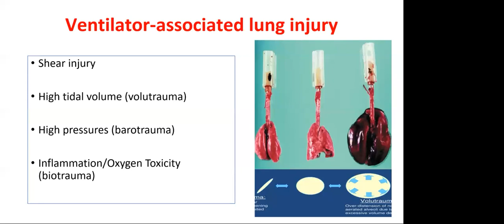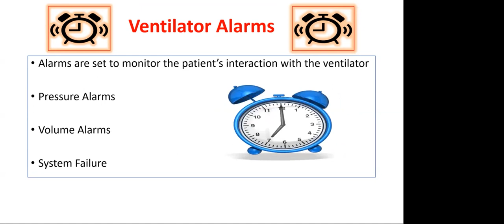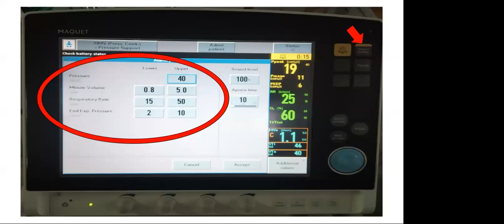So coming to the alarms. Alarms are mainly set to monitor the patient's interaction with the ventilator. There are alarms like pressure alarms and volume alarms. I already showed you the alarm profile, and I'm showing it again. Once you press here, alarm profile, you will come to pressure, minute ventilation, respiratory rate, and expiratory pressure. When do you want to get alerted? Case by case, you have to see, and the treating physician has to set the alarm profile.